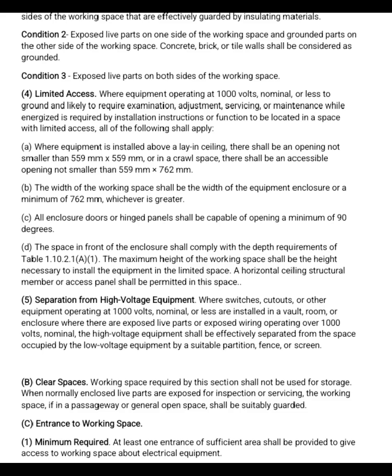Number 5. Separation from high voltage equipment. Where switches, cutouts, or other equipment operating at 1000 volts nominal or less are installed in a vault, room, or enclosure where there are exposed live parts or exposed wiring operating over 1000 volts nominal, the high voltage equipment shall be effectively separated from the space occupied by the low voltage equipment by a suitable partition, fence, or screen.